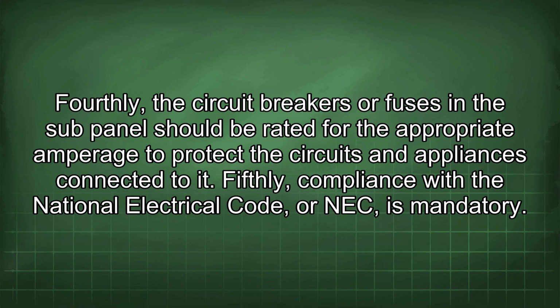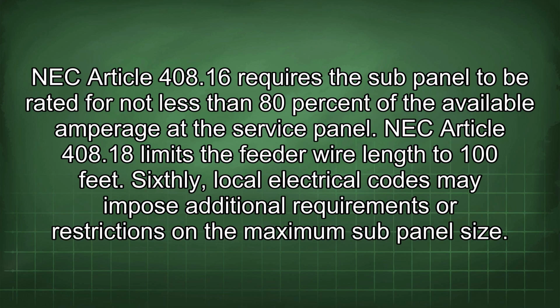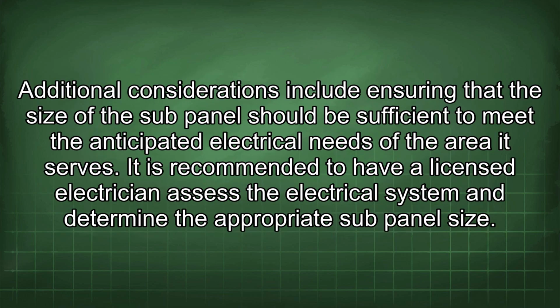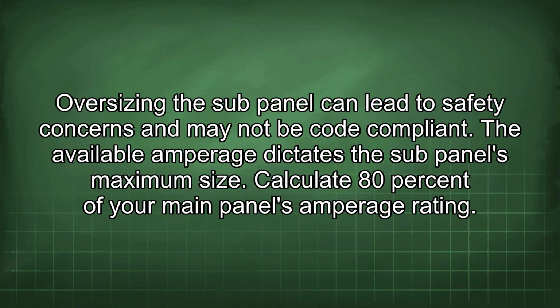Fifthly, compliance with the National Electrical Code, or NEC, is mandatory. NEC Article 408.16 requires the sub-panel to be rated for not less than 80% of the available amperage at the service panel. NEC Article 408.18 limits the feeder wire length to 100 feet. Sixthly, local electrical codes may impose additional requirements or restrictions on the maximum sub-panel size. Additional considerations include ensuring that the size of the sub-panel should be sufficient to meet the anticipated electrical needs of the area it serves. It is recommended to have a licensed electrician assess the electrical system and determine the appropriate sub-panel size. Oversizing the sub-panel can lead to safety concerns and may not be code compliant.